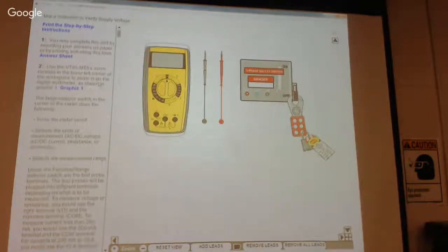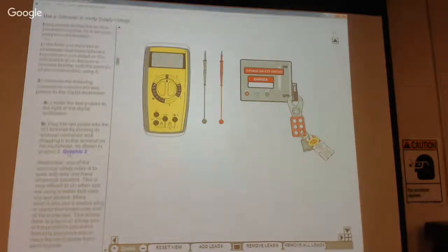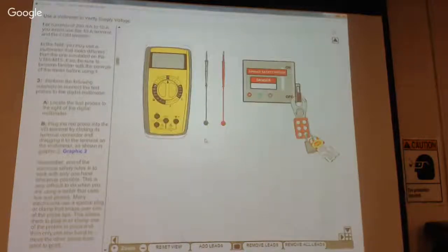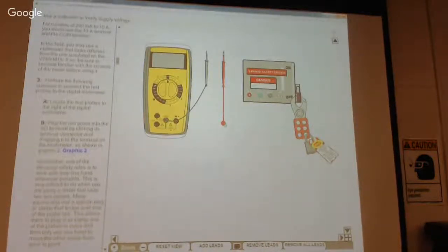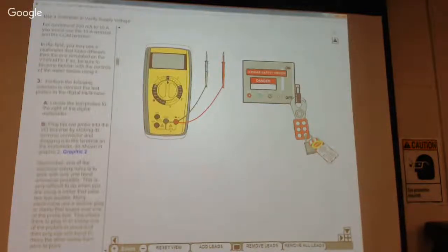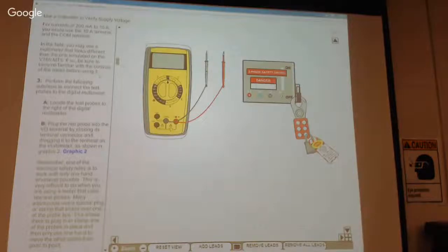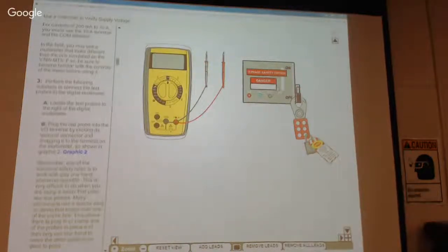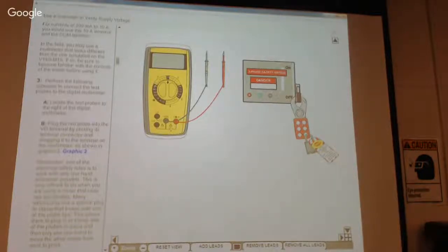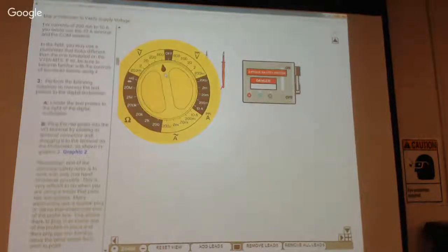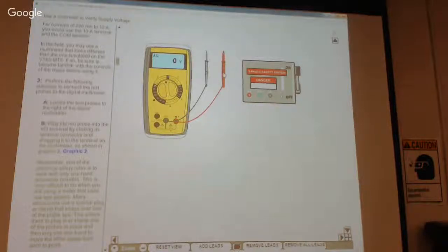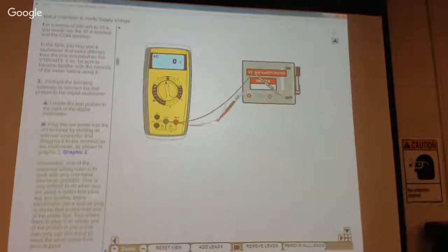So typically what we're going to do is go through here, and we're going to locate the test probes. We're going to connect them here, here, and have a diagram here somewhere. Okay. We're going to remove our lockout. Now we have power right here. We can come over here. We're going to put this on 600 volt AC. We're going to come over here. Typical disconnect. You want to check to ground, which will be our neutral, and see what we have here.